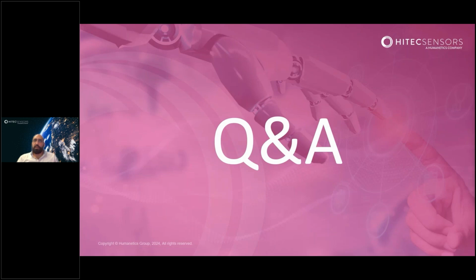Follow-up question on semiconductors: do we expect stability of semiconductor-based sensors? With our proprietary methods for temperature compensation, we've seen our semiconductor gauges be fairly stable. There are some effects, for example light, that could affect semiconductor gauges, so using a proper protective coating, which is dark, pretty much eliminates the light effect. There's a lot of factors: long curing time, how you wire things together, and a proprietary formula for temperature compensation used to balance the bridge properly for perfect temperature compensation. We've worked a tremendous amount of time on this, about 3 years at HITEC, doing research and development to develop that process.